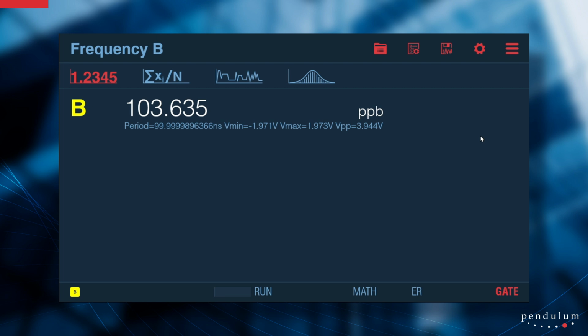As you have noted, it is very fast and easy to configure the CNT-100 series frequency analyzer to perform simple conversions of results, which will save you a lot of time. The instrument allows you to apply scaling, inversion, and offset functions to the measurement results. Additionally, it is possible to specify user-defined measurement units for the converted values.